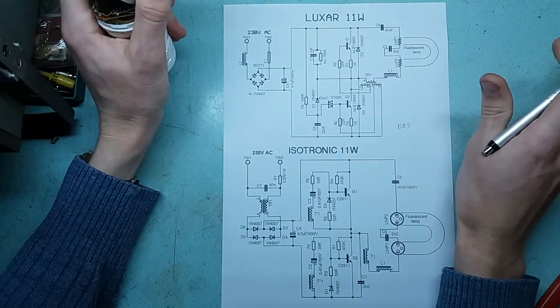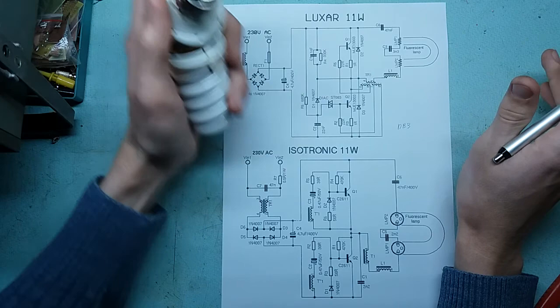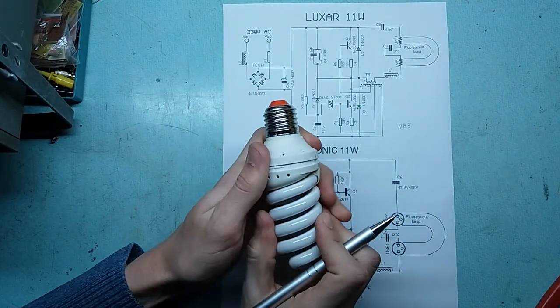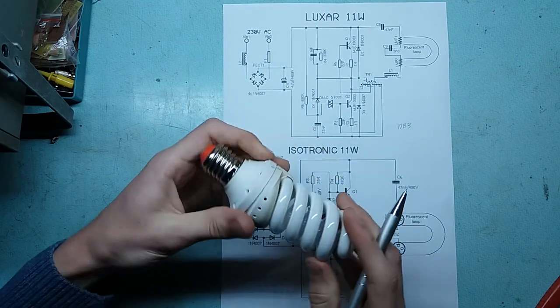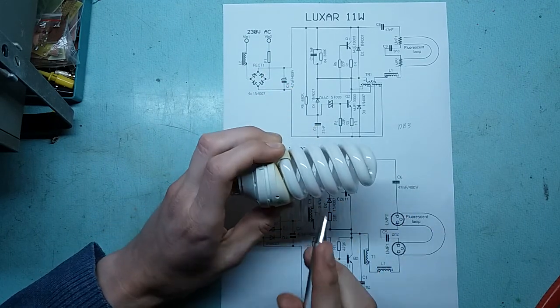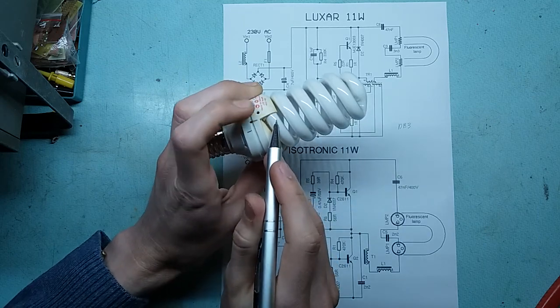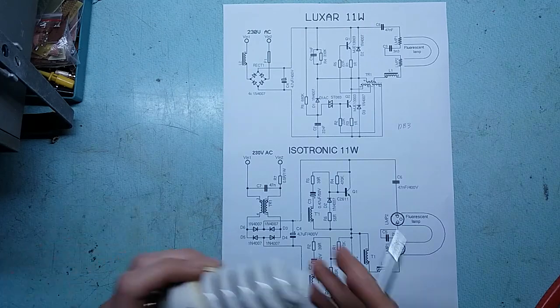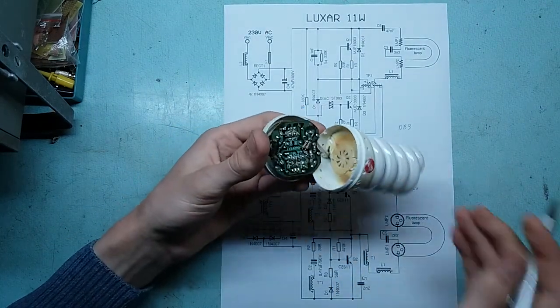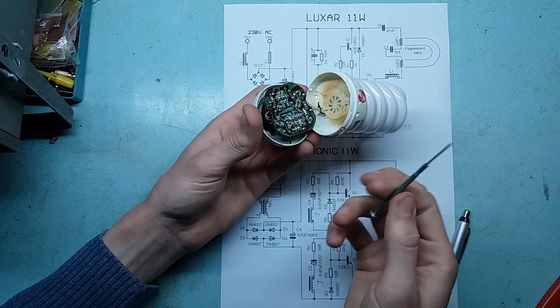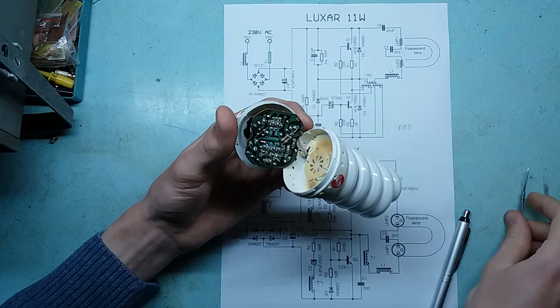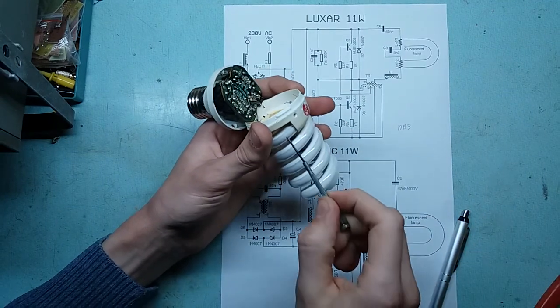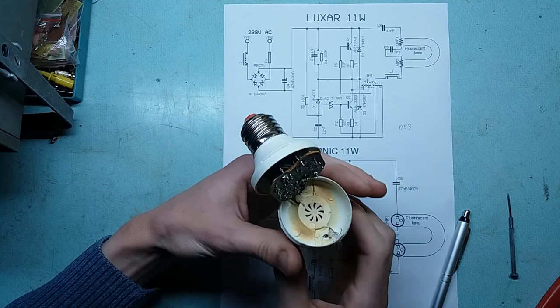So let's get to it. Let's say you have a tube, you have a lamp or a ballast, you plug it in and nothing happens. It doesn't do anything. It doesn't blink, it doesn't glow red in these ends which are close to the base. Absolutely nothing. You take it out, you crack it open with a little flat blade screwdriver. This thing held by clips. Just be careful not to crack the tube and that's about it.